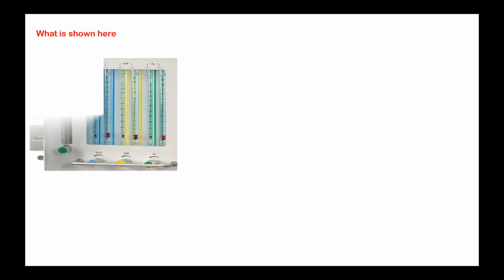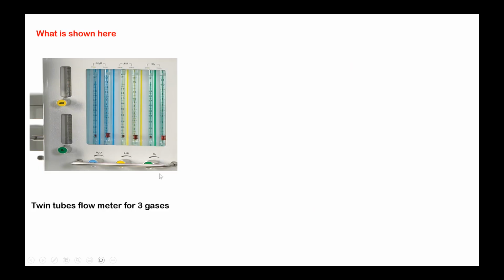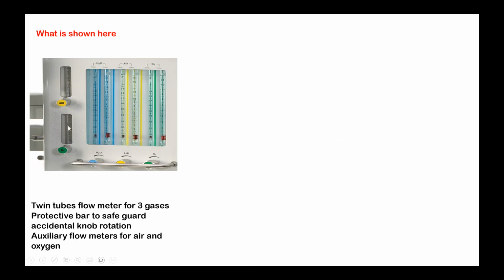What is shown here? Forget this portion, because this also is a twin flow tube, which we have already seen. Apart from that, what is this? It is called a twin flow meter for three gases, plus a protective bar in front of it to prevent accidental movement of the knob, and there is an auxiliary flow meter for air and oxygen.